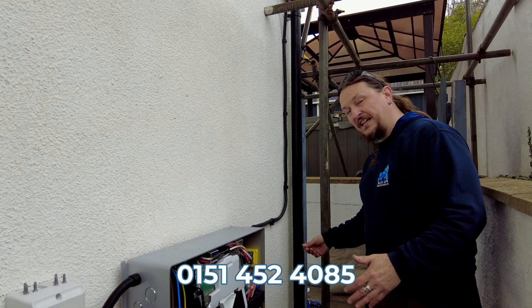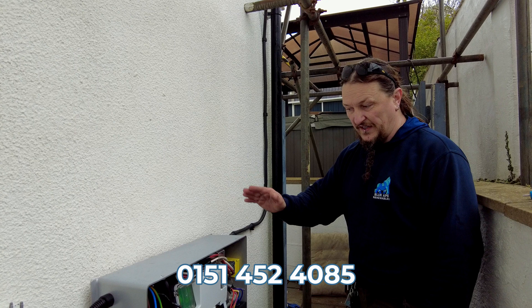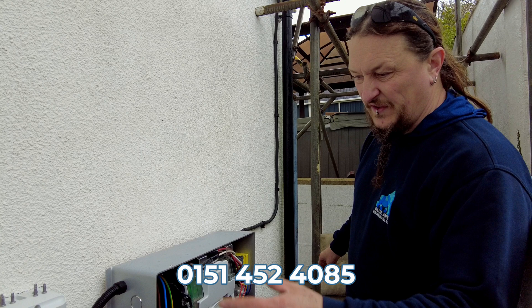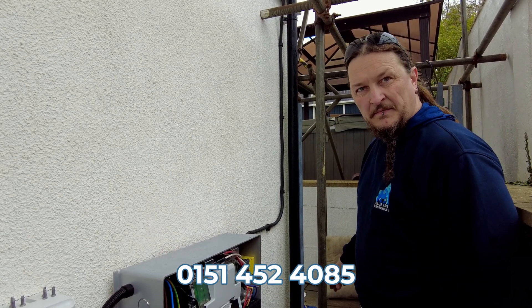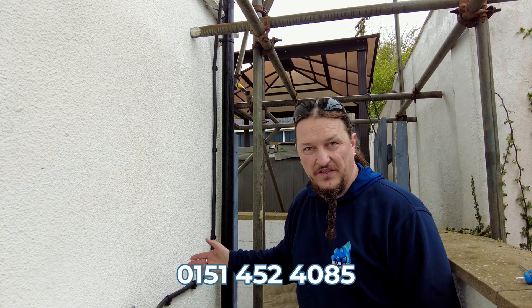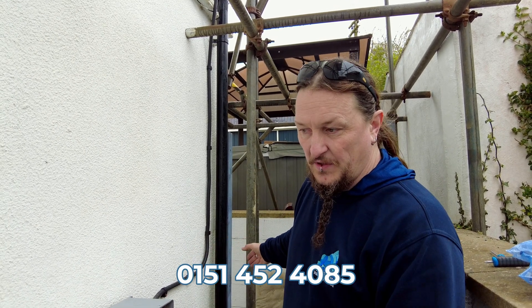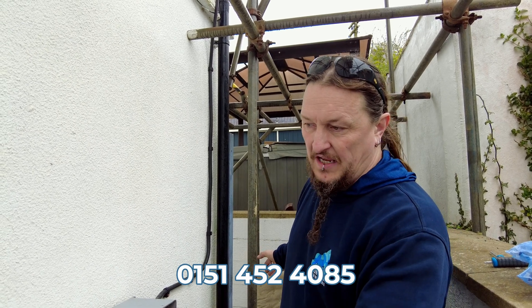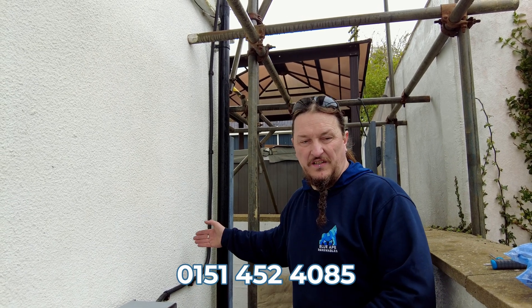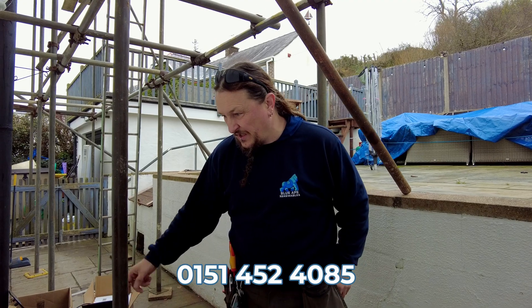It's really installer-minded — a lot of thought has been put into that. Even the holes where the cables come in are already ready to knock out. They've prepared a variety of different sizes and stated they don't want any holes drilled. There's a built-in DC isolator, although we've added our own point of isolation in case any work needs to be done. For the MCS compliance, we've also added an external AC isolator. We've tested the PV strings for their voltage, open circuit voltage, and short circuit current — they're just fine.